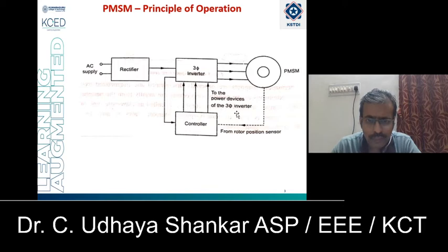When the armature winding draws a current, the current distribution within the stator armature winding depends upon the rotor position and the turning on process of the devices in the control circuit. The sine wave voltage output is to be applied to the three-phase winding system in such a way that the angle between the stator flux and the rotor flux is kept close to 90 degrees in order to achieve the maximum generated torque. To meet this criterion, the motor requires the electronic control for its proper operation.